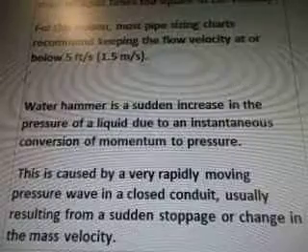So what is water hammer? A water hammer, or more generally fluid hammer, is a pressure surge or wave caused by the kinetic energy of a fluid in motion when it is caused to stop or change direction suddenly. The movement of liquid mass in a pipe is kinetic energy, which is proportional to the mass of liquid times the square of the velocity. For this reason, most pipe sizing charts recommend keeping the flow velocity below 5 FT/S or 1.5 M/S.